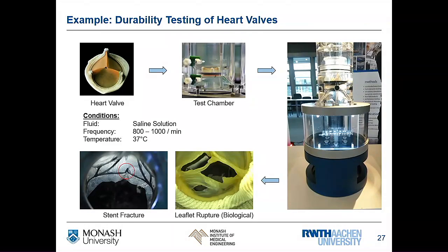And you have seen that it worked pretty fast. If you say a manufacturer has to prove, as an example, that a valve lasts at least 5 years, I said before, 40 million cycles a year is roughly our heart at rest, times 5, 200 million cycles. That means you have to prove that your valve works for 200 million cycles. And you cannot sit there and wait 5 years until you have done that. So of course we try to do accelerated testing. That means you accelerate the cycle rate and try to get it not in 5 years, but in 0.5 years, because you do it times 10, for example.